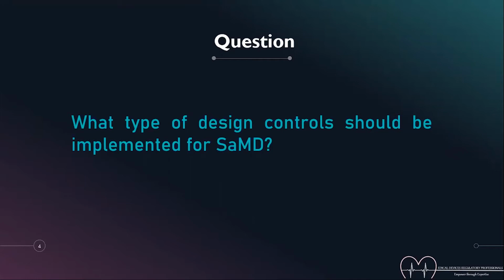Now, for software, this V model is a bit more complex, and normally we tend to use a standard. That's the software lifecycle process for medical devices. The standard is called IEC 62304, and this gives a very good guidance on what you need to establish when you want to document software as a medical device, or any type of software approach. Now, what is said in this standard is how you decompose the software depending on the risk it has and what type of deliverables you need to have according to the risk class of the software.